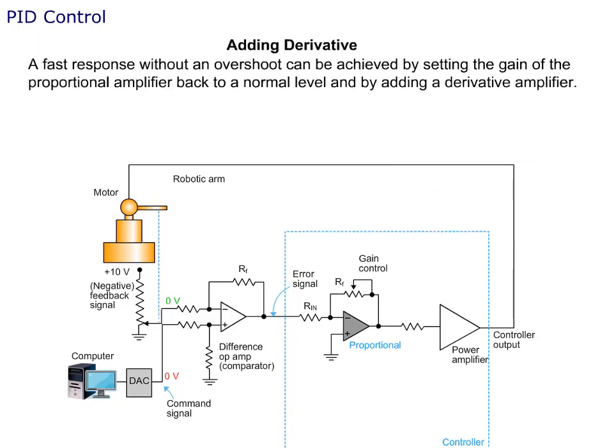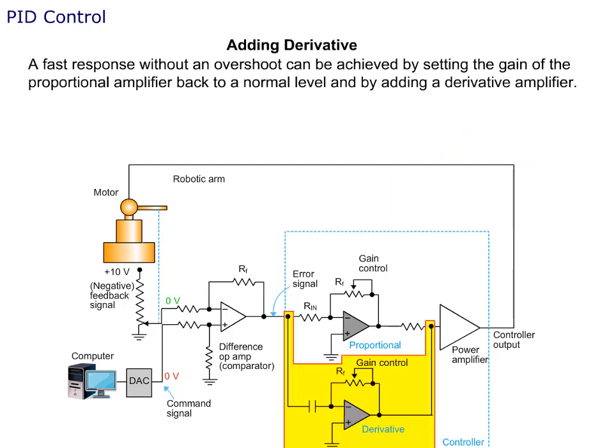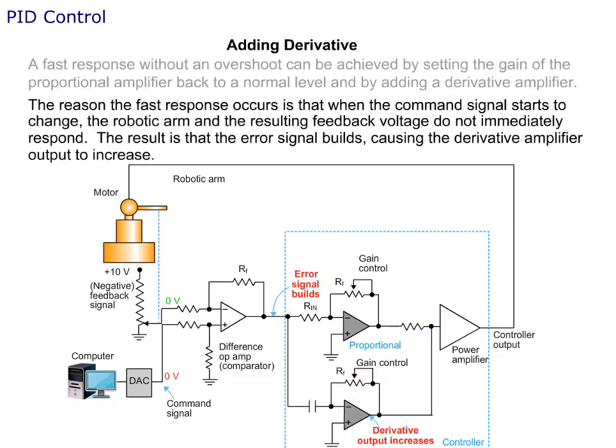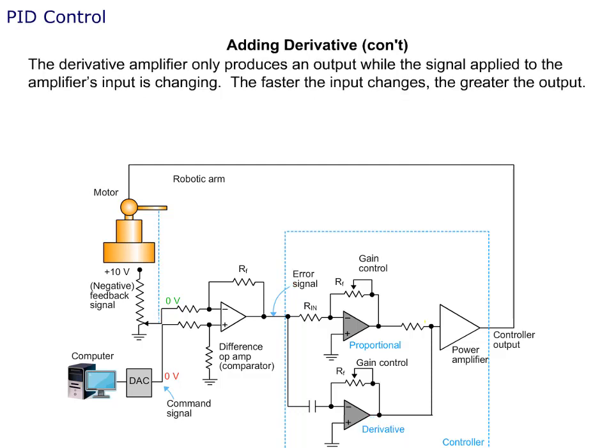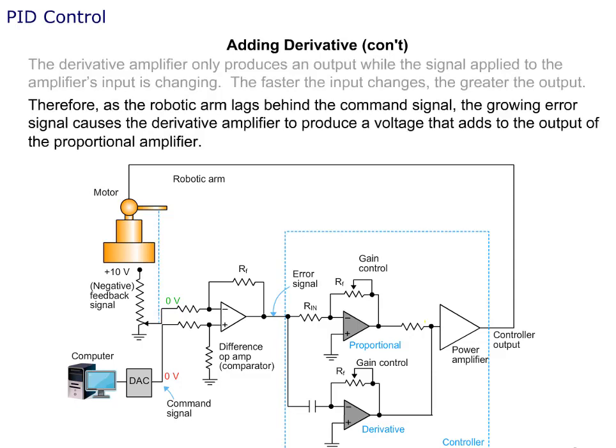A fast response without an overshoot can be achieved by setting the gain of the proportional amplifier back to a normal level and by adding a derivative amplifier. When the command signal starts to change, the robotic arm and the resulting feedback voltage do not immediately respond. The result is that the error signal builds, causing the derivative amplifier output to increase. The derivative amplifier only produces an output while the signal applied to its input is changing — the faster the input changes, the greater the output. Therefore, as the robotic arm lags behind the command signal, the growing error signal causes the derivative amplifier to produce a voltage that adds to the output of the proportional amplifier.